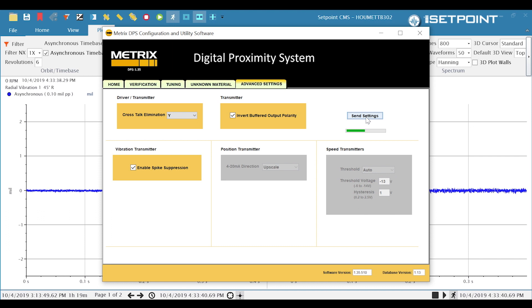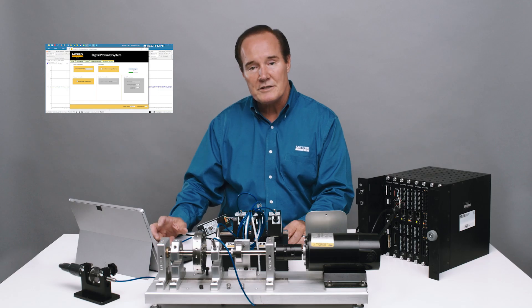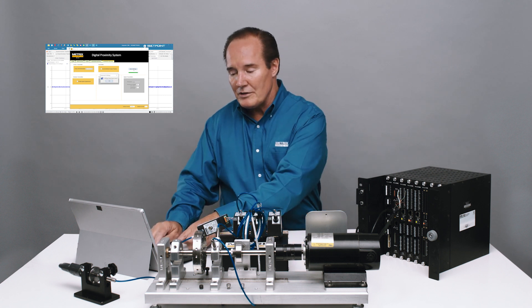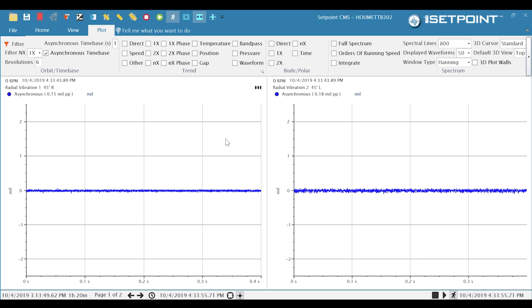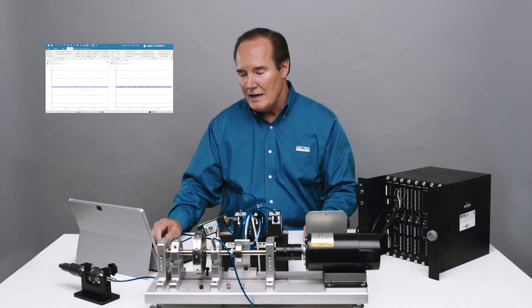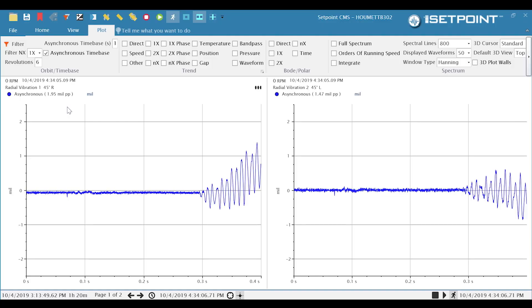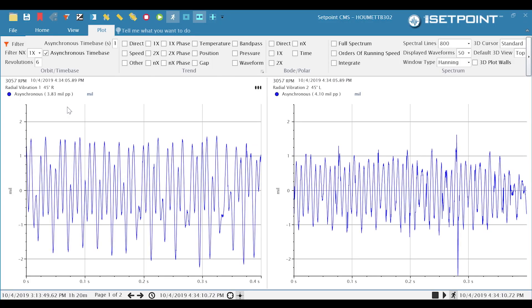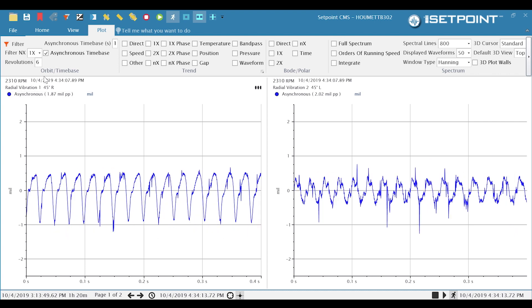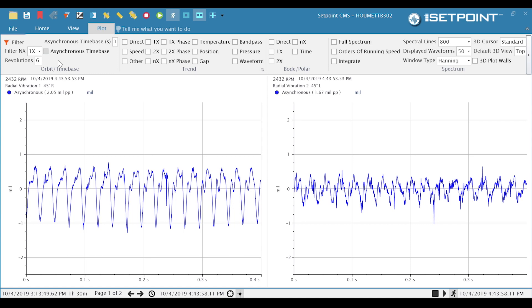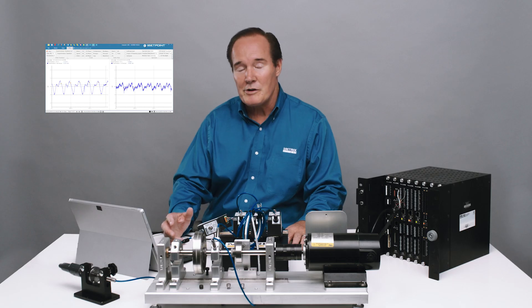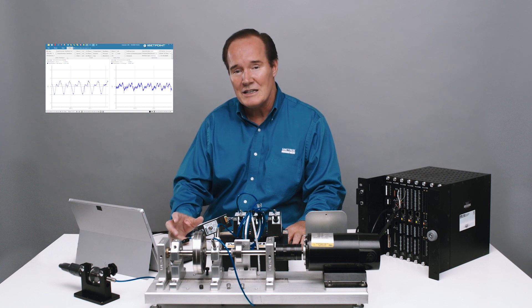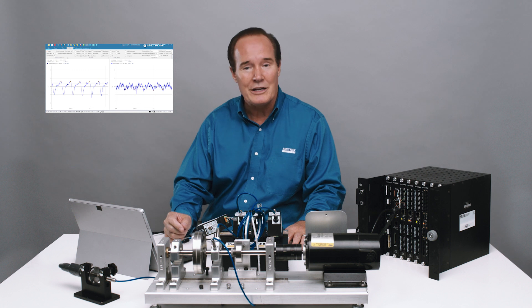You can see how it's updated. We'll let it finish updating and make sure the DPS is fully changed. Then we'll go ahead and look at the vibration signal — and that shows you crosstalk elimination. You can see now our ambient noise level is down to 0.18 and 0.15 mils peak to peak. That's very good — excellent for a transmitter. Let's go ahead and start up the machine and see if it behaves any better. Look at what the phase trigger looks like now — it's a much cleaner signal, much better than before, and we've removed all that noise. That's the power of being able to eliminate crosstalk, and you do that by shifting the frequency.